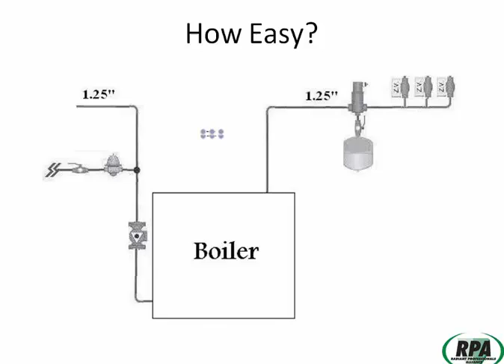It's actually this easy. You just simply connect the supply and return together to create the secondary loop. In this case, we relocated the zone valves to the returns. We installed an ECM variable speed delta P circulator on the system so that it would react to the zone valves. We installed the water feed on the point of no pressure change where it belongs. And on the primary loop, we put in a 3-speed circ. And in that way, we can move the water through the boiler at the correct rate without any problems.